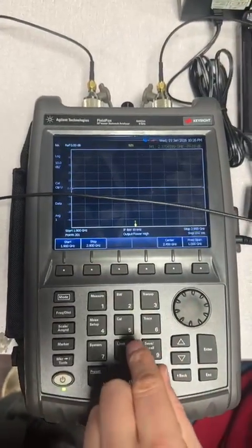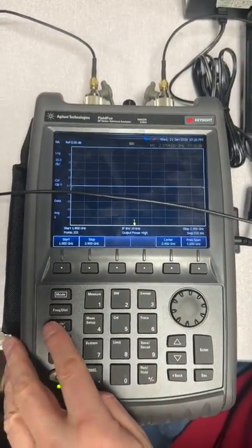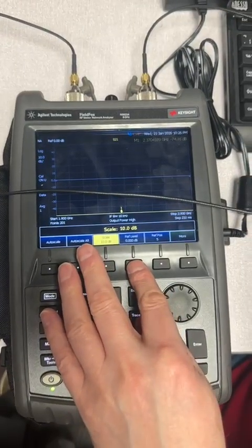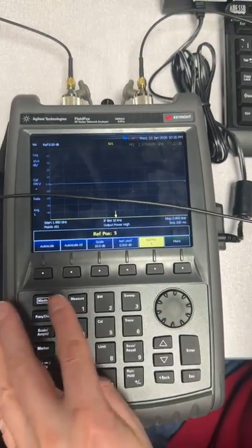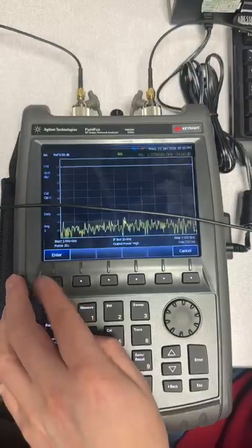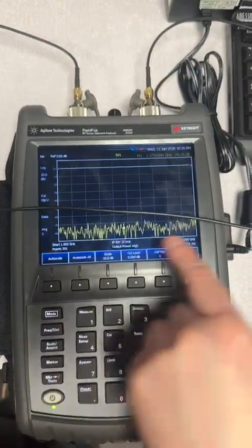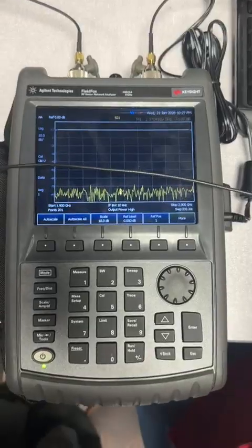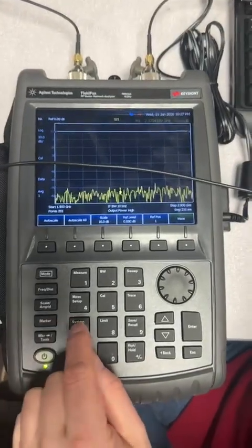So okay, let's go back, because I'll show you something now. Go back to amplitude. Oh, what about measure setup? Let's take that to 1. Yeah, that might be measure setup. You see it's updating now. You can see the noise floor changing. It's because the hold was on, so just watch for that. What button did we say we were going to press? Measure setup.